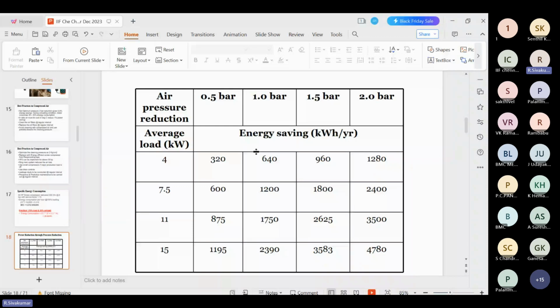Here, no investment is needed. That's why the compressor pressure band should be optimized in the industry. Based on whatever the process demand requirement is, the compressor pressure band is to be fixed. Otherwise, we are losing more energy. This chart depicts the various energy losses associated with this high pressure setting.